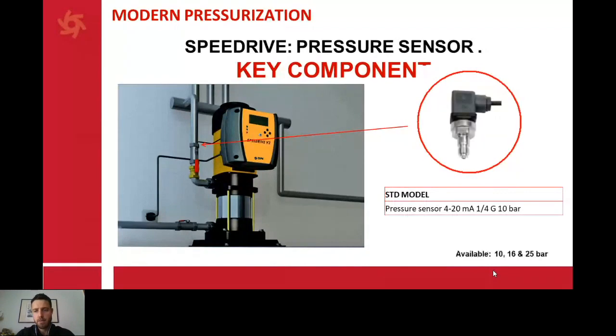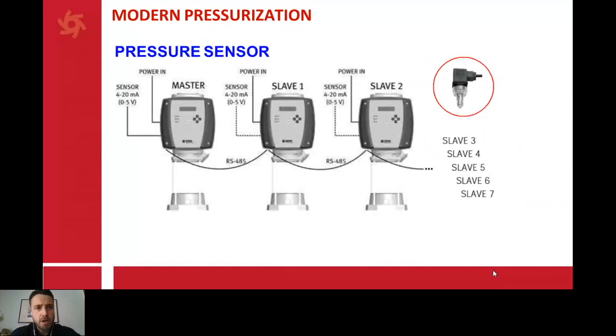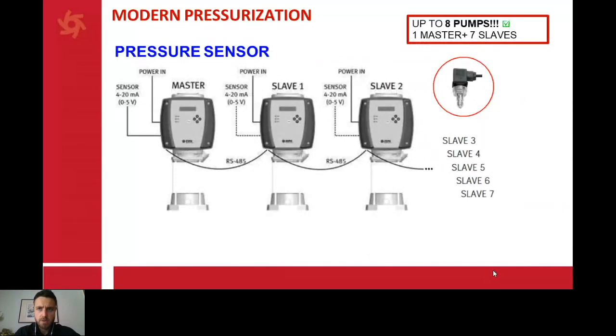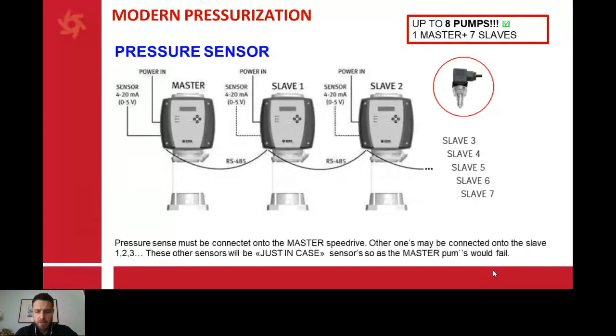The standard model is 10 bar, but we also have availability of 10, 16, and 25 bar. Okay, pressure sensor. We are talking about up to 8 pumps, 1 master and 7 slaves. And we have these security sensors. We normally set the booster set with 1 pressure sensor, but more sensors can be added to the booster set. If we have 2, it's better, because in case the first sensor fails, the second will come into functioning. So the booster set will never stop, and we will continue giving the water to the installation.